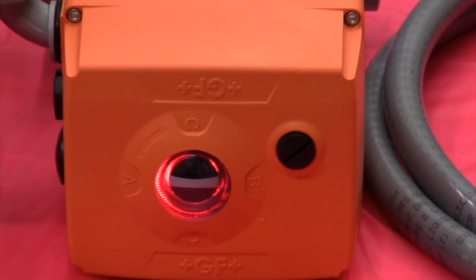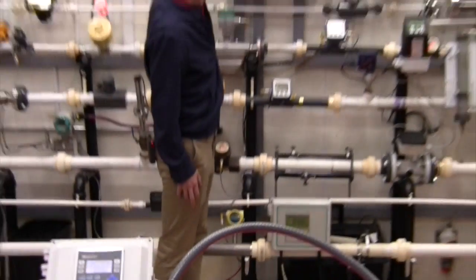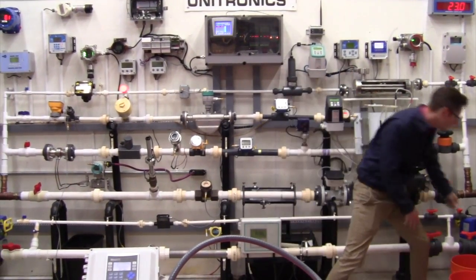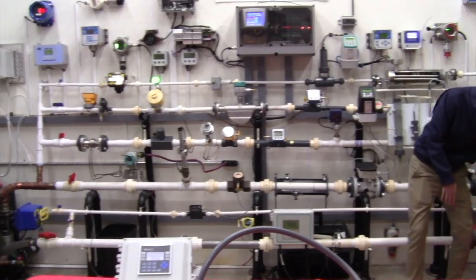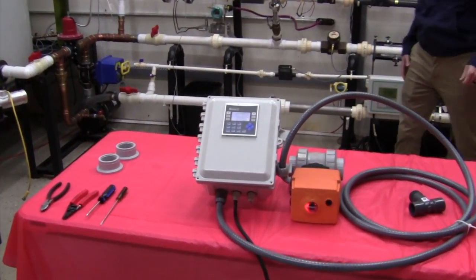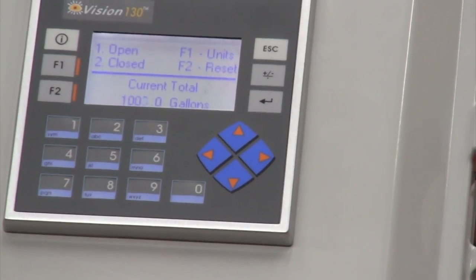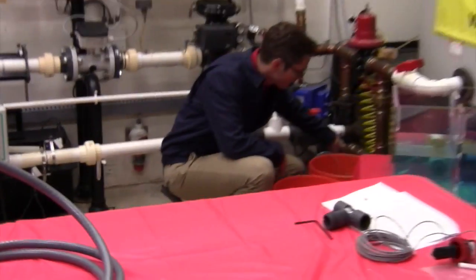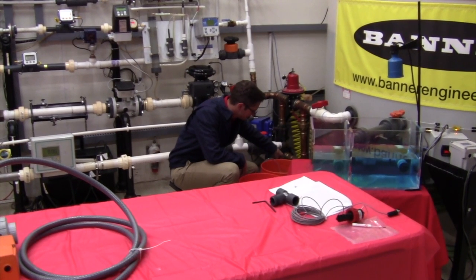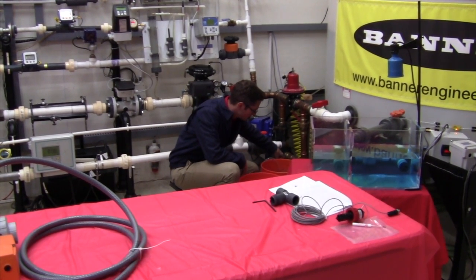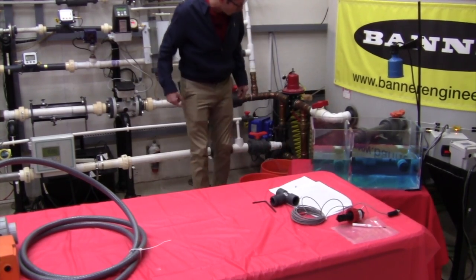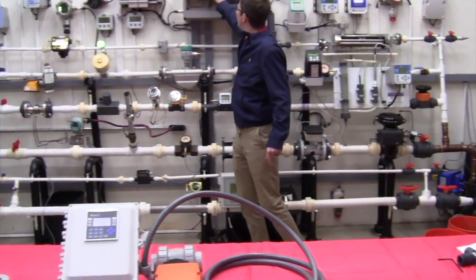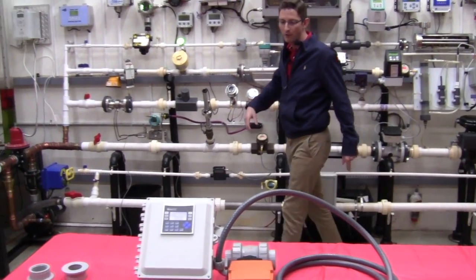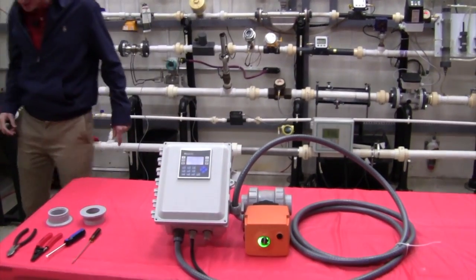So again, if that valve were installed in this line, it would be open, we'd be ready to flow. So I'm going to turn my pump on, open my hand valve, and we're now filling our 5-gallon jug. All right, now our 5-gallon bucket's full. I turned my hand valve off, turning my pump off. Now we should be done totalizing.